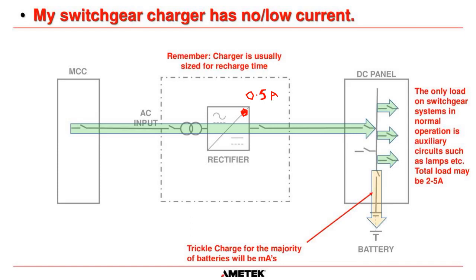But, for example, on switchgear systems, the only load that you have is the auxiliary circuits, so lamps and maybe some relays, very, very low current. So you could, in theory, only have 0.3 amps, because if the battery is fully charged, you could have a very small amount of current, milliamps, to trickle charge the batteries, and then your load circuits could be low. So in truth, in normal operation, the output of your charger is okay if it's 0.3 amps, if that's what the load circuits are asking for. So you are going to alarm because the low current threshold is 0.5 amps.